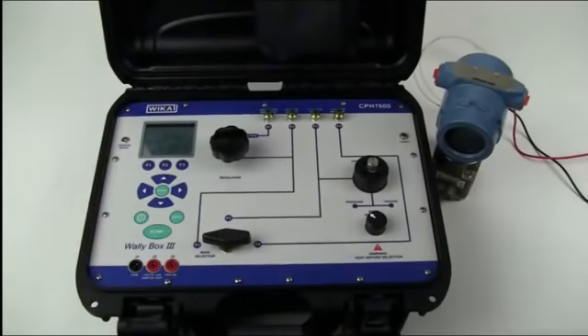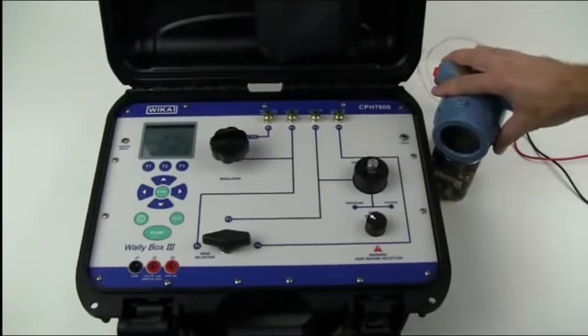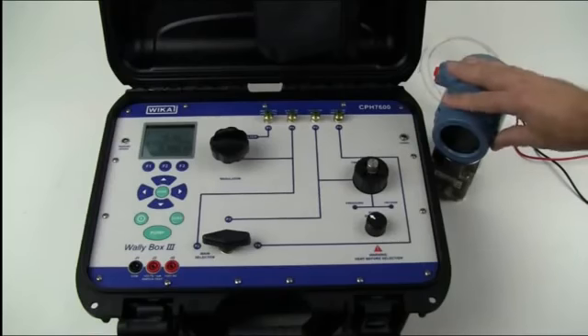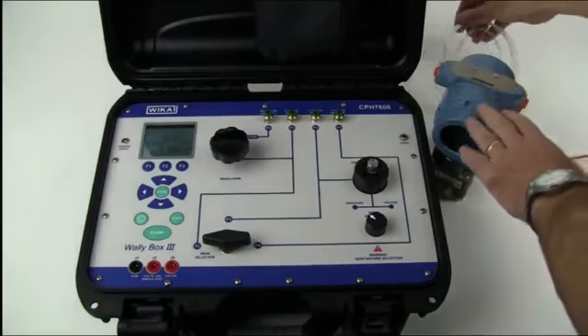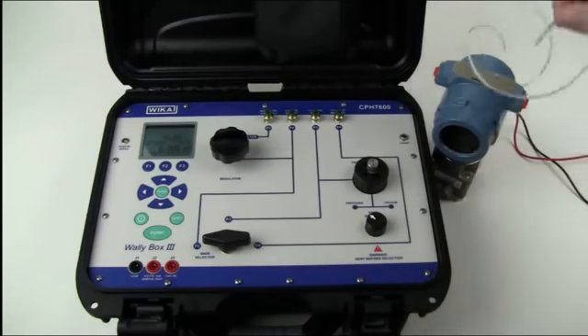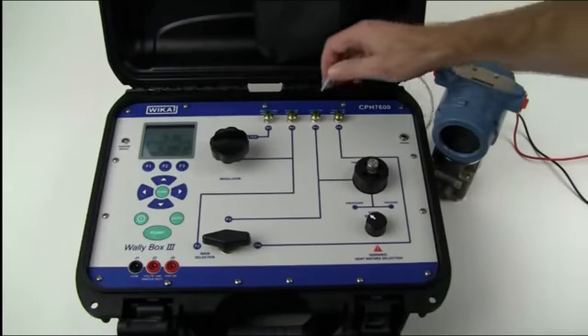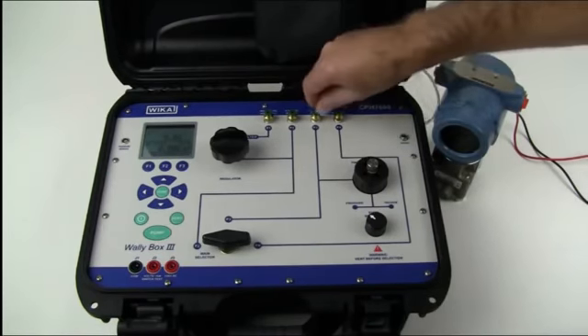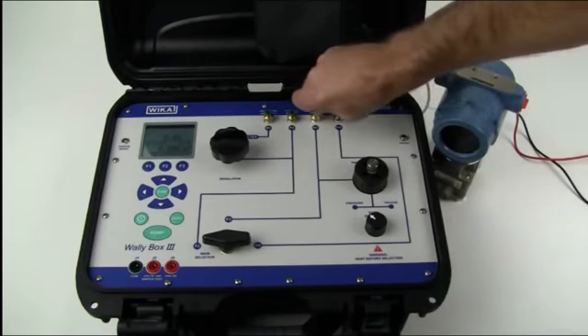We are now going to calibrate a pressure transducer using the Wally Box. The pressure transducer in this application is rated to 300 psi, so we need to connect the pressure transducer to position P3 so that we can use the internal pump to source the pressure to the transducer. We will then also need to connect the milliamp signal of the transducer to the common J1 and to give 24 volts to the transducer to J3.